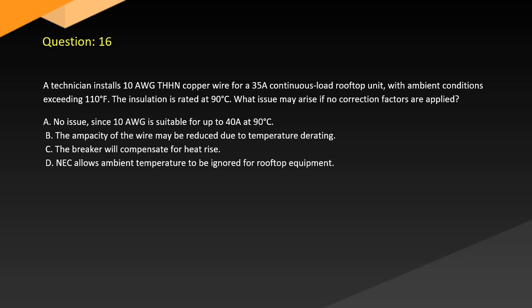Question 16. A technician installs 10 AWG copper wire for a 35 amp continuous load on a rooftop unit with ambient conditions exceeding 110 degrees. The insulation is rated at 90 degrees. What issue may arise if no correction factors are applied? A. No issue, since 10 AWG is suitable for up to 40 amps at 90 degrees. B. The ampacity of the wire may be reduced due to temperature derating. C. The breaker will compensate for heat rise. D. NEC allows ambient temperature to be ignored for rooftop equipment.